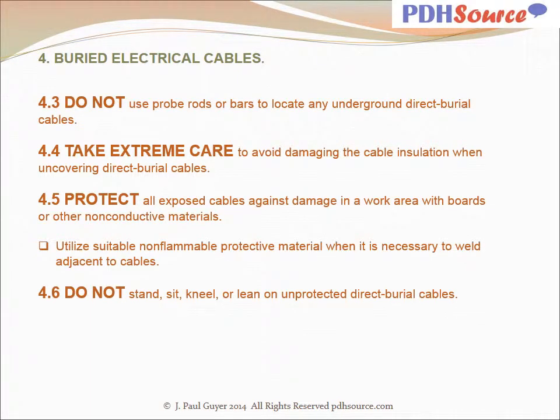Do not use probe rods or bars to locate any underground direct burial cables. Take extreme care to avoid damaging the cable insulation when uncovering direct burial cables. Protect all exposed cables against damage in a work area with boards or other non-conductive materials. Utilize suitable non-flammable protective material when it is necessary to weld adjacent to cables. Do not stand, sit, kneel, or lean on unprotected direct burial cable.